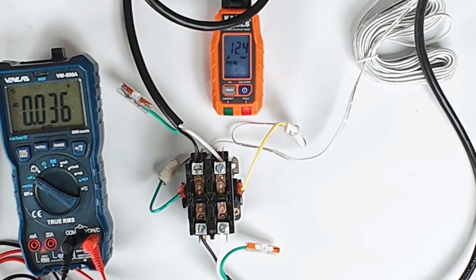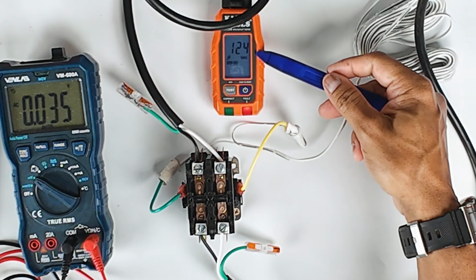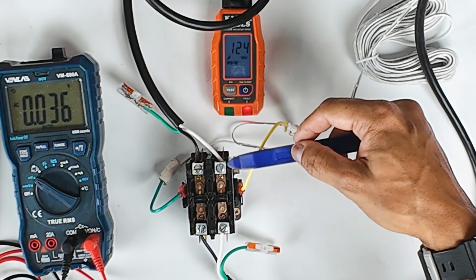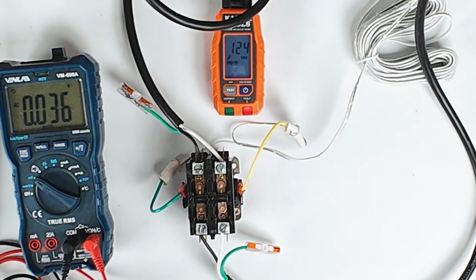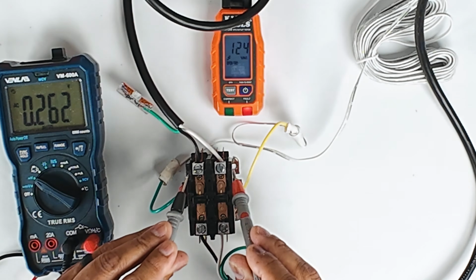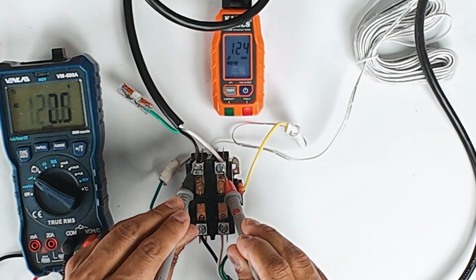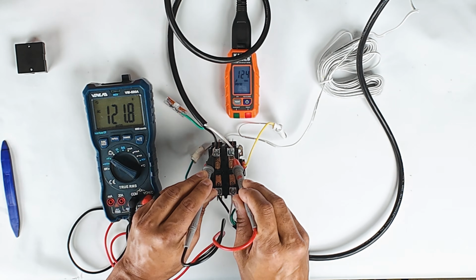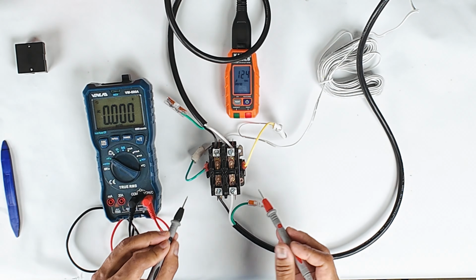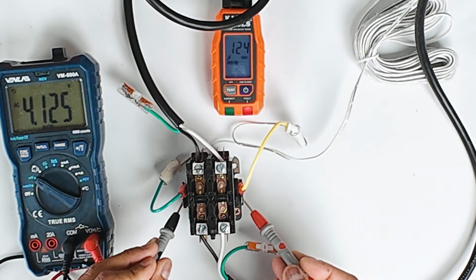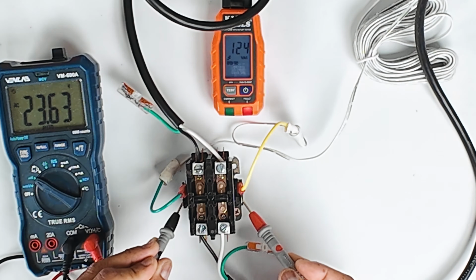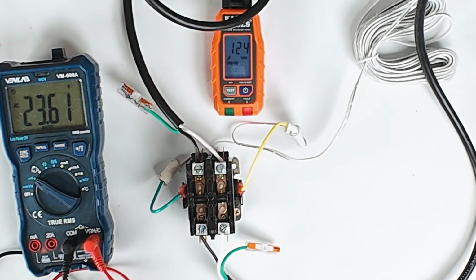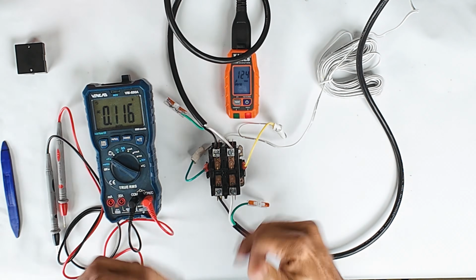just like that. And now when you hear it close, you can see 120 volts is now passing through on these terminals up here and going to the meter. I can measure here. As you can see on my meter, we have 120 volts on the top side. And if I measure across the coil on this side, we should get 24 volts. And we have 24 volts.